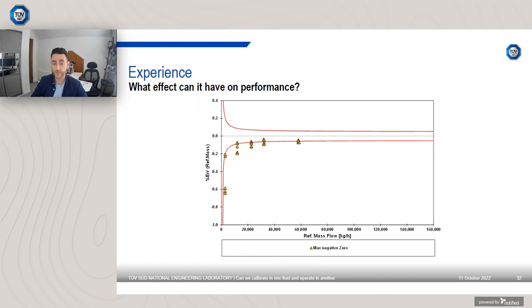If you're operating a gas flow meter, remember, this is a 3-inch device, up to 160,000 kilograms per hour. The gas flow range was up to nominally 36, so up to this, I included an extra point here, but up to approximately here. And you can see that the zero effects are dominating, and we're down at about 0.2% deviation at this flow rate, and 0.6% here. That's out of specification even for potentially a gas flow meter at these flow rates, and close to it at these flow rates, because the zero effects are starting to dominate.